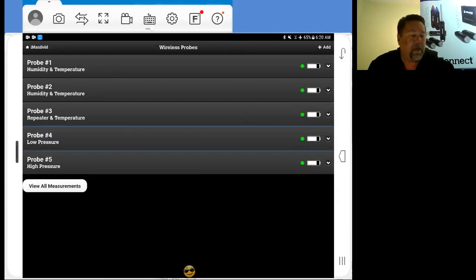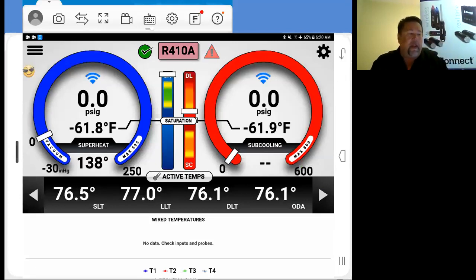Now let's take a look at our manifold right quick. Up here in the upper left-hand corner. As you can see, we have no pressures. There's our saturation temperatures. We're not hooked in right now. There's all of our active temperatures, and we have them all there. We have our suction line, our liquid line, our discharge line temperature, and our outdoor air temperature. So we're ready to roll with this. We can hook this up.